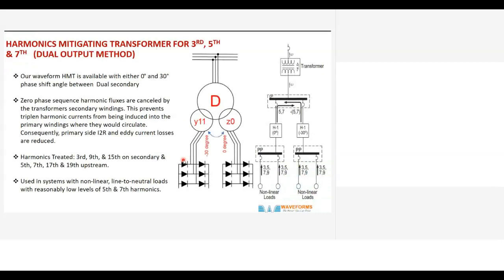when you have a drive with a 6 pulse diode, we have a transformer called Y11. Okay? So that is a 30-degree phase shift. One output is 30-degree phase shifted, and the other is a 0-degree zigzag transformer, which is also called a zero sequence impedance transformer. When you connect two loads like this, you'll find 3, 5, 7, 9 all eliminated. The third harmonic gets eliminated in the zero sequence winding, and the fifth and seventh get cancelled out in the bus bar. The fifth and seventh will still flow from here, and when they flow in the opposite direction at 180-degree phase shift, they cancel out automatically.